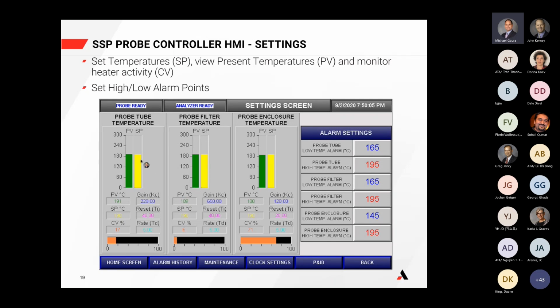And again, you have the set point right here and here and here for the probe tube, the probe filter, and the probe enclosure respectively. Next to it, the green line is the present value, which is what we're seeing here: the temperatures are running up near that 190 C, as they should be. And then you can confirm that down here, looking at the present value shown right here, as well as the set point shown right here. And then down below, you can actually see how hard the individual heaters are working. So this is what kind of pull on the heater is occurring in order to maintain the temperature at those various locations.